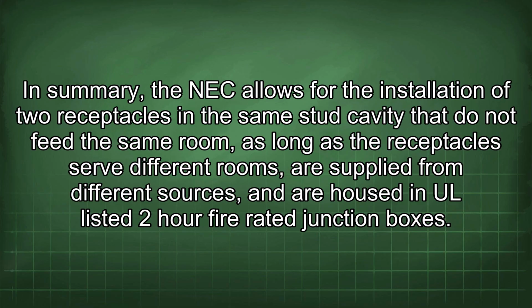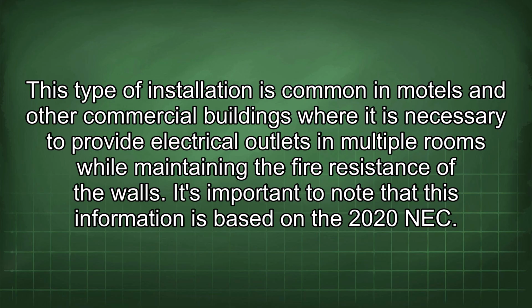In summary, the NEC allows for the installation of two receptacles in the same stud cavity that do not feed the same room, as long as the receptacles serve different rooms, are supplied from different sources, and are housed in UL listed 2-hour fire rated junction boxes. This type of installation is common in motels and other commercial buildings where it is necessary to provide electrical outlets in multiple rooms while maintaining the fire resistance of the walls.